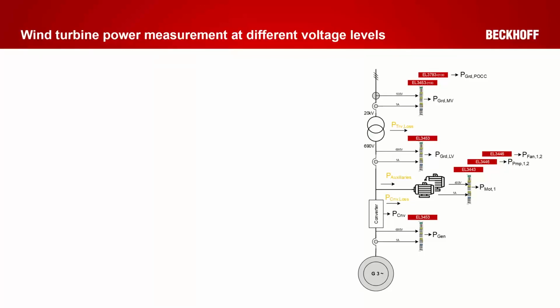One typical application I see, and I think the common way to implement it, is our wind turbine with the drivetrain and with the generator, converter, and main grid connection. So we will start here at the generator side. Directly at the stator of the generator, we can measure, maintain and protect the generator with one of our terminals. Maybe it's a 690 volt generator type. You can use a directly connected EL3453, and we will use the current transformer to measure the power, harmonics, imbalances, and so on.